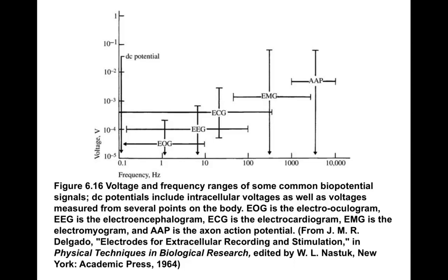The issue is that in the clinical environment, not only do you have power lines, you often have a significant amount of equipment powered by 60 hertz, and it's very difficult in a crisis situation to isolate all of that as far as capacitive coupling. So that can be a challenge in an ER or critical care type environment.